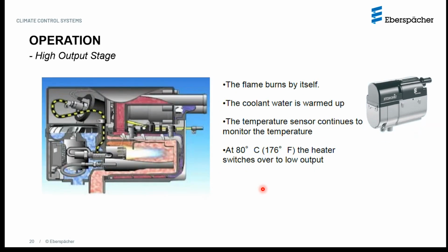Now, once it starts up, the flame is burning independently. Your coolant is getting warmed up. The temperature sensor, or the inlet sensor, is monitoring the temperature, and at about 176 degrees, now, this is for the first generation heater, this could be slightly different on the third generation, but there will be a switching temperature. This is the switching temperature at which the heater switches to a lower output. In case of the third generation, as you know, it has a variable output. So it will also switch, but these switching temperatures, there'll be many.